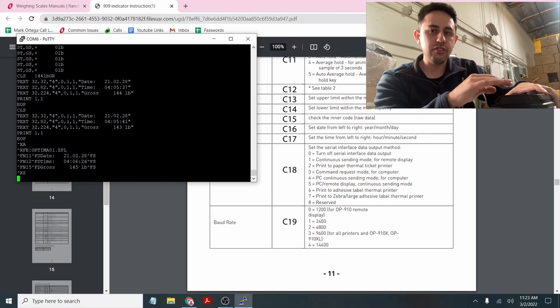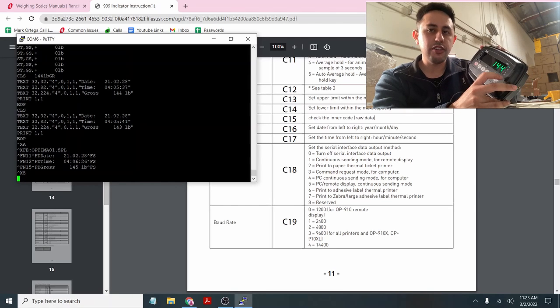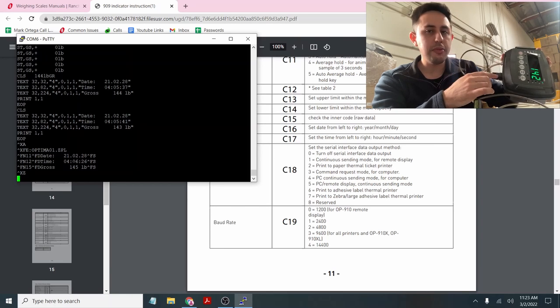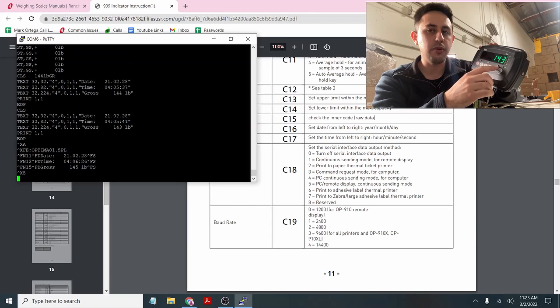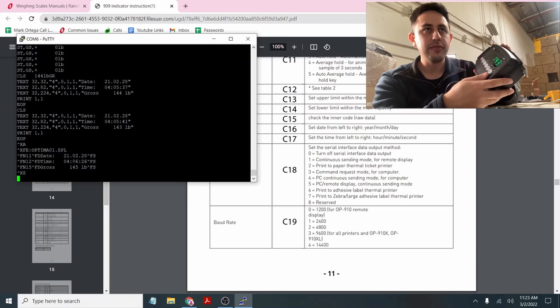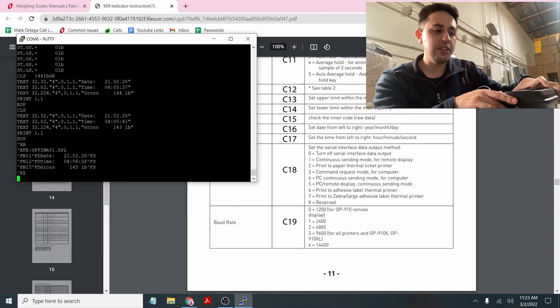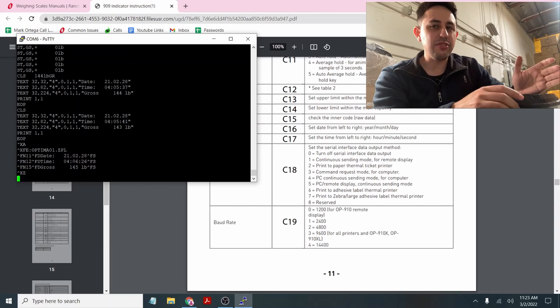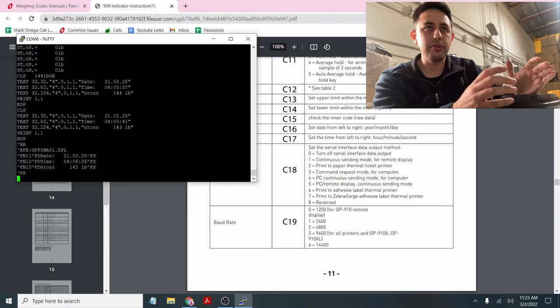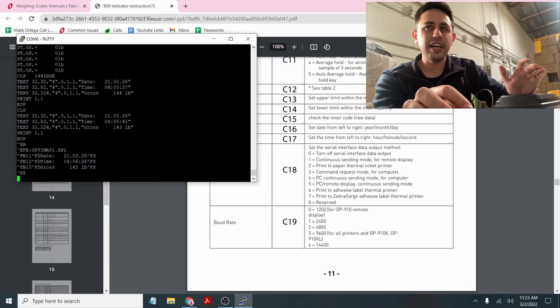That will output continuously, and you'll know if it's working or not. If during the wiring process it's not working, then maybe you flipped the transmit and receive by accident. Flip those two, reconnect it. If it's just DB9, you don't have to worry about that, but if it's hardwired, maybe you flipped it by accident. So make sure you have the proper transmit and receive, because there are only 3 connections, so it's not that many possibilities. And that's kind of it.